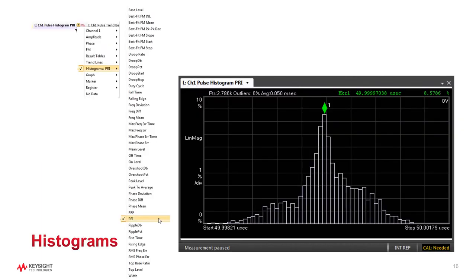If you have a large population of pulses that are supposed to have roughly the same pulse width or pulse repetition interval, you can evaluate the accuracy of your equipment by plotting a histogram. Here we show a histogram of pulse repetition interval. Since the MXG timing is extremely accurate in this experiment, you can see from the x-axis that this does not vary very much.